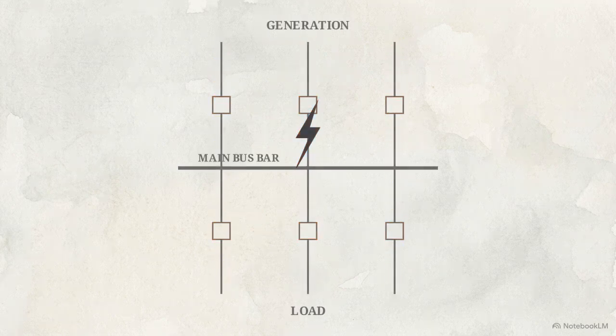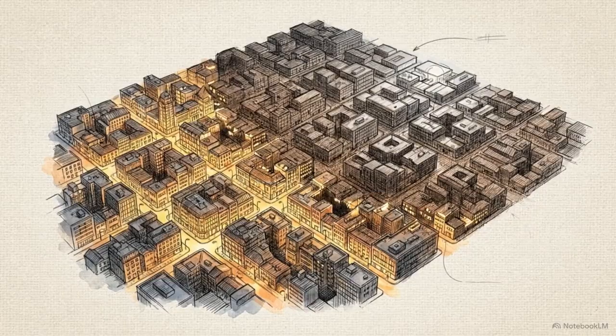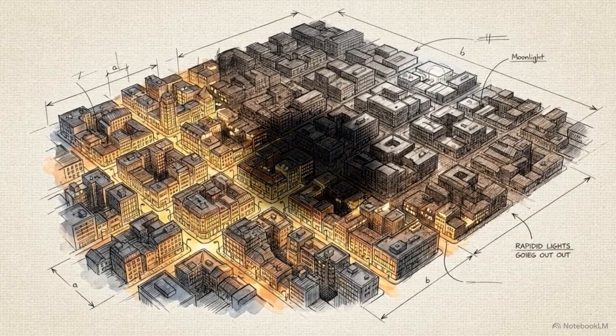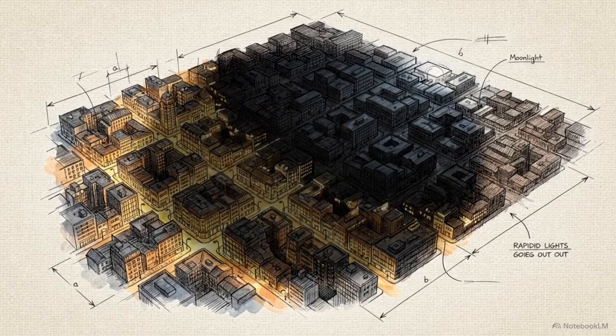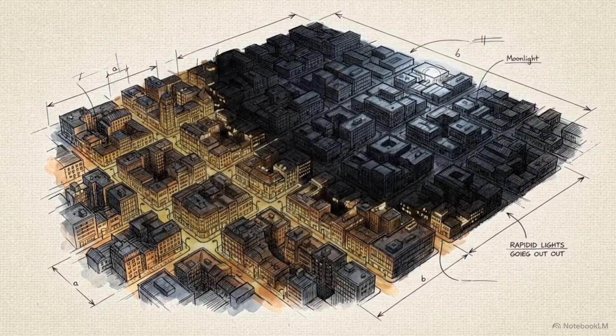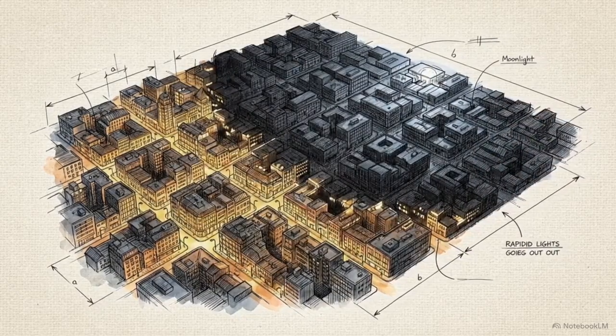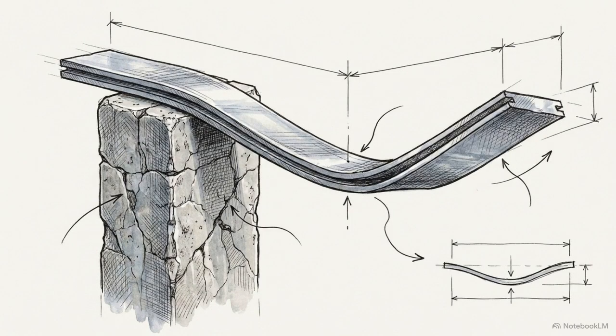But if a localized fault, like a flashover, occurs on this bus, the mechanical reaction is absolute. To clear it, every connected circuit breaker must trip simultaneously. The consequence is severe, a total localized blackout, dropping all connected loads instantly and destabilizing adjacent network nodes relying on that power flow. The single bus topology is economically ideal, but structurally fragile. For critical high-voltage nodes handling vast amounts of regional power, it is entirely insufficient.